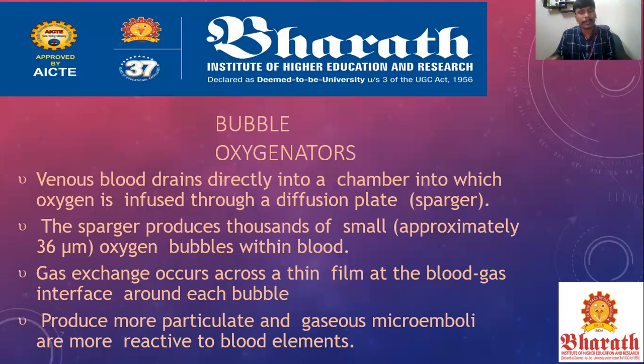When the bubble is made under some pressure and O2 is embedded into that bubble, the already existing CO2 is removed from that blood. In this way, deoxygenated blood is converted into oxygenated blood in the bubble oxygenator. It also has the ability to produce more particulate gaseous microemboli and is more reactive to blood elements. So it has high reactive sensitivity to the blood elements when compared with the membranous oxygenator.